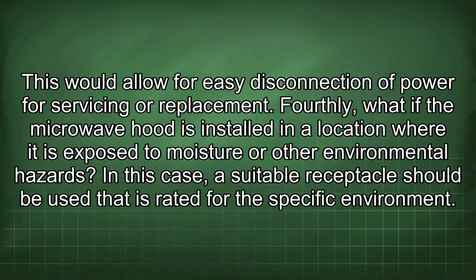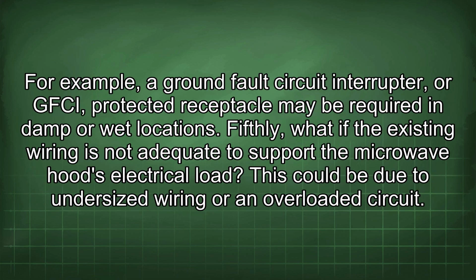Fourthly, what if the microwave hood is installed in a location where it is exposed to moisture or other environmental hazards? In this case, a suitable receptacle should be used that is rated for the specific environment. For example, a ground fault circuit interrupter, or GFCI, protected receptacle may be required in damp or wet locations.